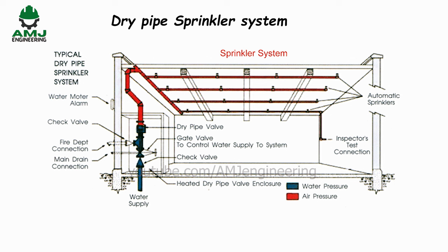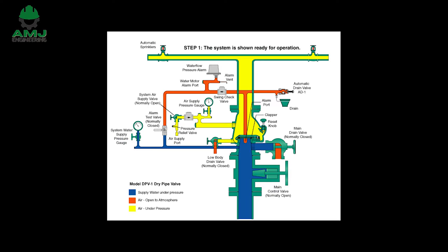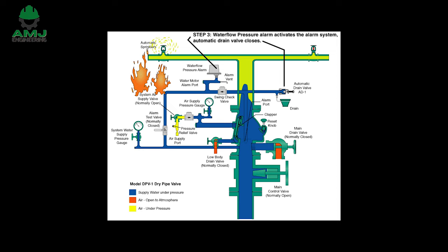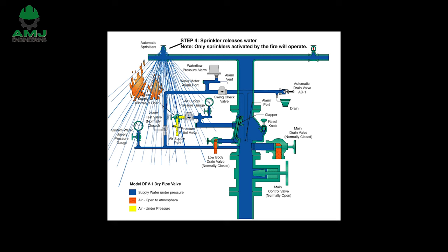Dry pipe fire sprinkler systems are very similar to wet pipe systems with one major difference: the pipe is not constantly filled with water. Instead, the water is held behind a dry pipe valve, usually some distance away from where the sprinklers are located. When the temperature at the ceiling becomes hot enough, the glass bulb or fusible link breaks. However, water isn't immediately available because the pipe is not water-filled. Air is released from the now-open sprinkler head, creating a drop in pressure causing the dry pipe valve to open and water to fill the system, then flow from the open sprinkler head.